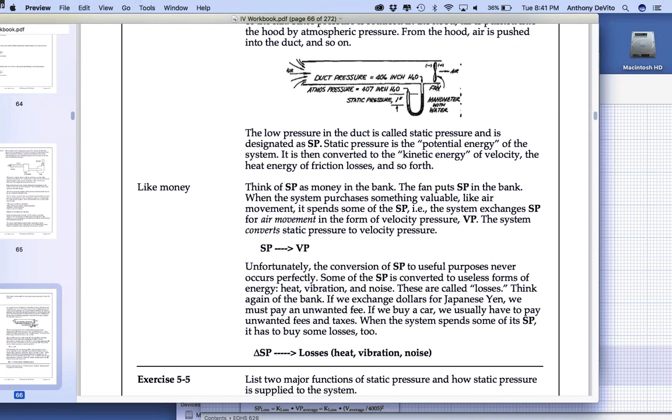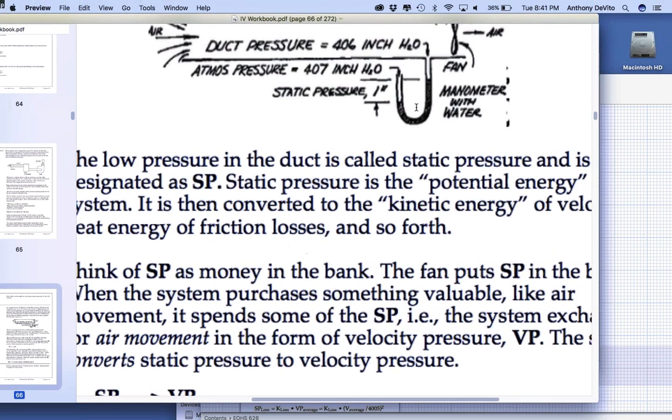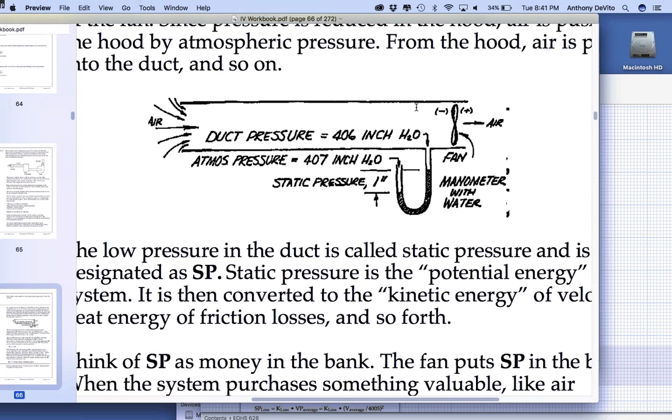Okay, so here's a measure of static pressure. Remember I said it measures the pressure from the side of the duct. The speed of the air doesn't influence the pressure. That's only measuring static pressure when you see that. Everybody agree with that? When you have an anemometer and when you have a pitot tube, it has two holes in it, one facing into the flow of air and the other one on the side, just like this is on the side. So the velocity of air is not pushing into that hole, so that hole is measuring the static pressure. This hole is measuring the total pressure. Remember, the static pressure acts in all directions, so it's measuring both. That's why you have to subtract one from the other. You're getting a measurement from a pitot tube of total pressure and static pressure. So if you want the velocity pressure, you have to have either the device calculate it for you or you have to calculate it.